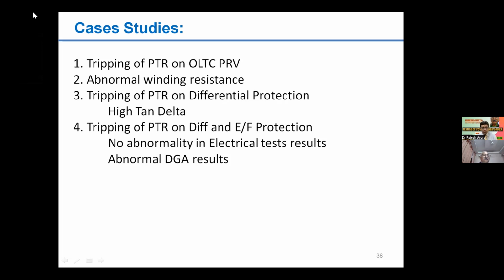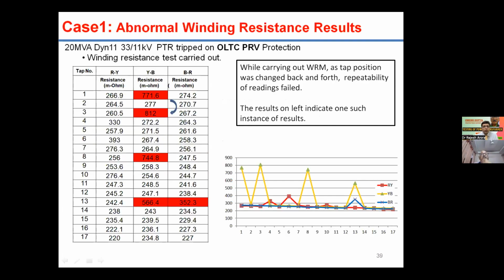Thank you. Good evening, everyone. Now we will discuss a few cases where we could diagnose faults in the transformers based on different tests, and severe damages could be prevented by timely action. So the first case I'm going to discuss is tripping of a 20 MVA power transformer on OLTC PRV protection. This transformer also had the automatic voltage regulator AVR in service, and when it tripped, we first checked for any kind of pickup in the overcurrent and differential relay, but no pickup was found. Thereafter, we proceeded for the testing of this transformer.